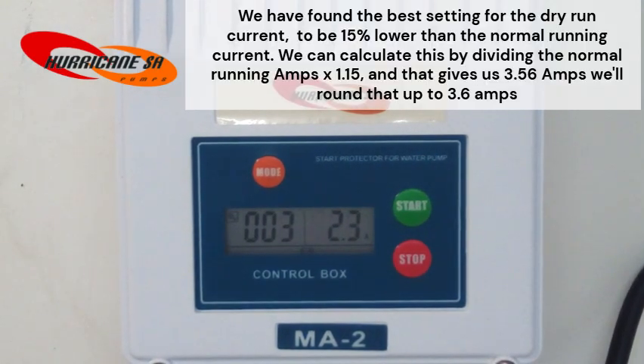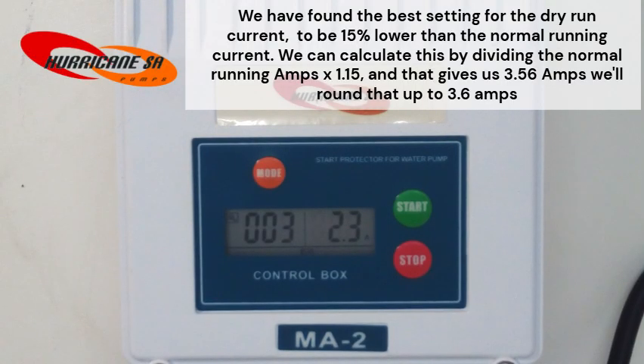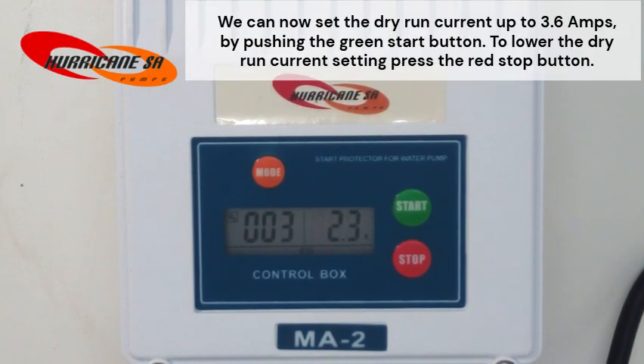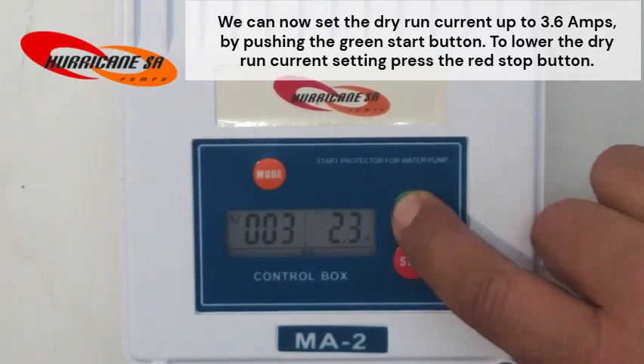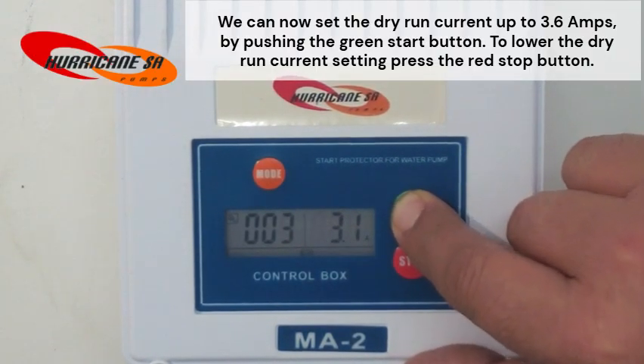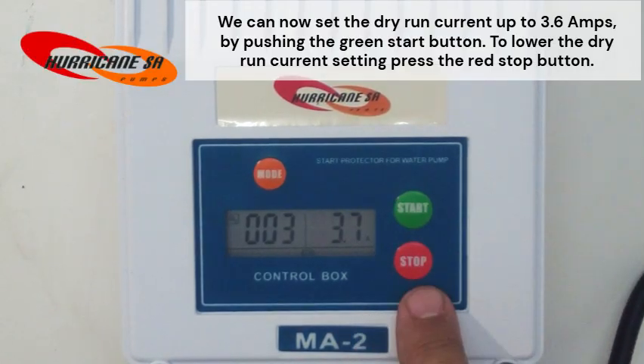We have found the best setting for the dry run current to be 15% lower than the normal running current. We can calculate this by multiplying the normal running amps by 1.15, and that gives us 3.56 amps. We'll round that up to 3.6 amps. We can now set the dry run current up to 3.6 amps by pushing the green start button. To lower the dry run current setting, press the red stop button.